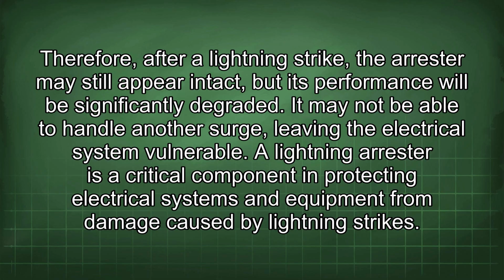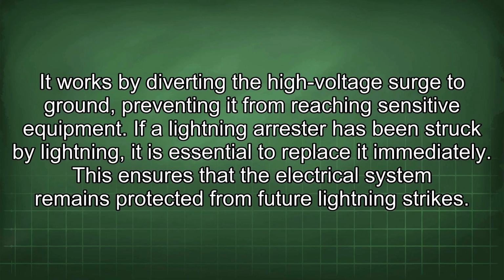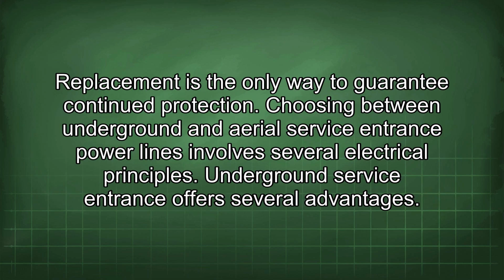A lightning arrestor is a critical component in protecting electrical systems and equipment from damage caused by lightning strikes. It works by diverting the high voltage surge to ground, preventing it from reaching sensitive equipment. If a lightning arrestor has been struck by lightning, it is essential to replace it immediately. This ensures that the electrical system remains protected from future lightning strikes. Replacement is the only way to guarantee continued protection.